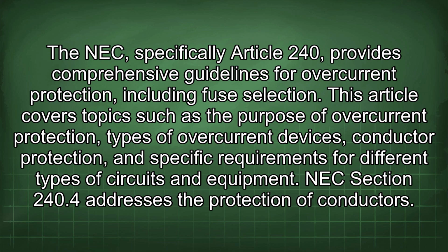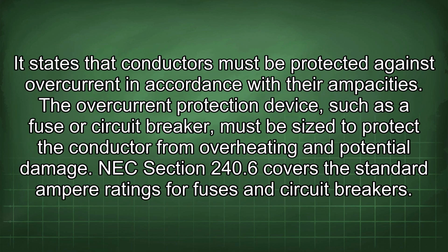NEC Section 240.4 addresses the protection of conductors. It states that conductors must be protected against overcurrent in accordance with their ampacities. The overcurrent protection device, such as a fuse or circuit breaker, must be sized to protect the conductor from overheating and potential damage. NEC Section 240.6 covers the standard ampere ratings for fuses and circuit breakers.